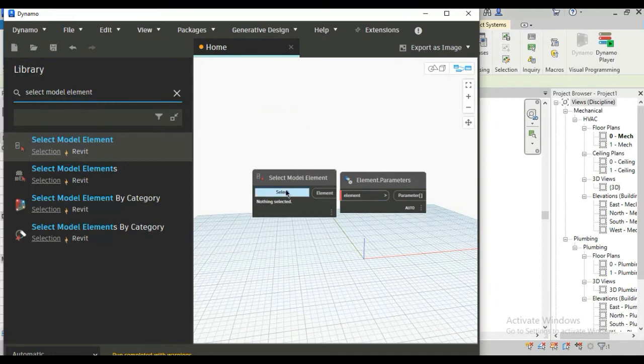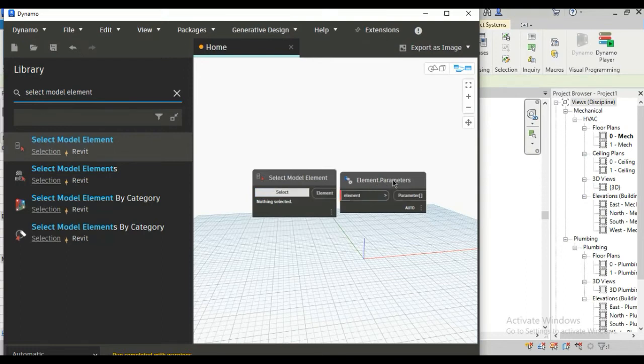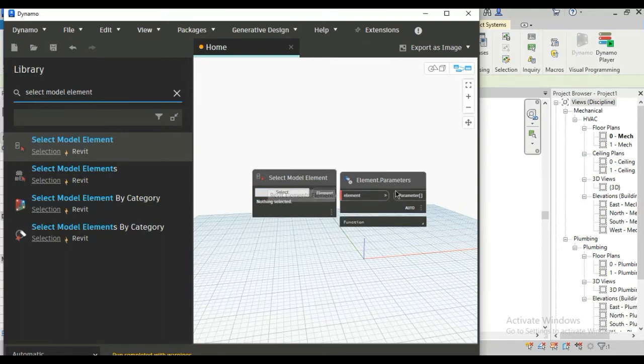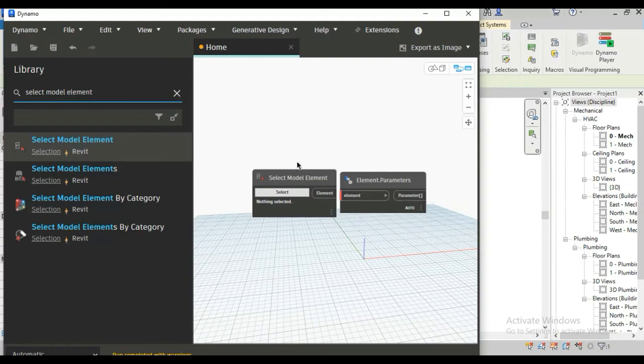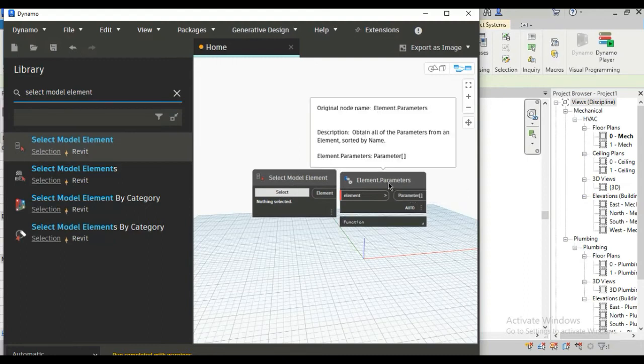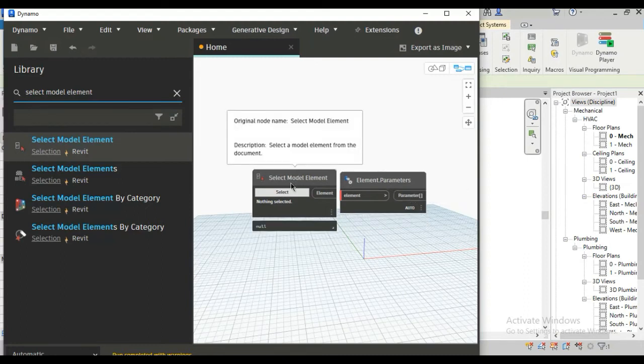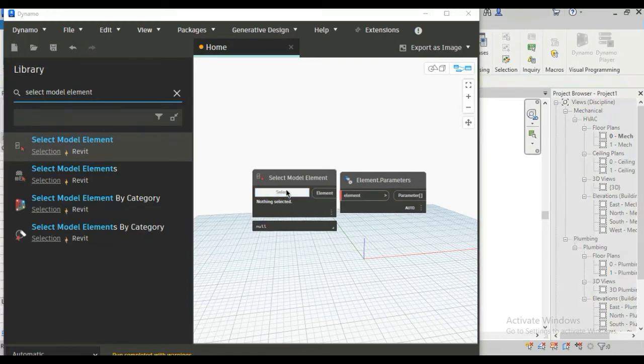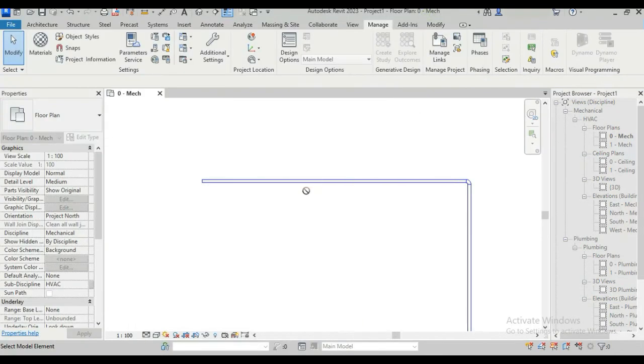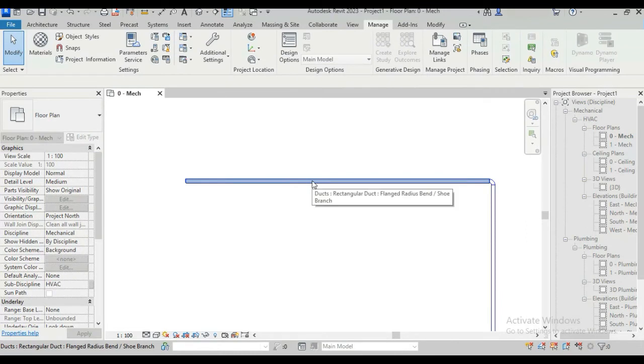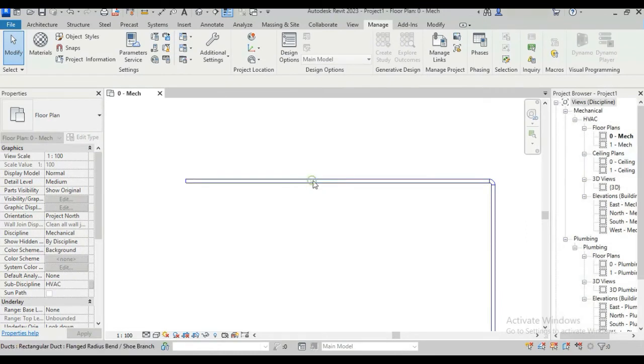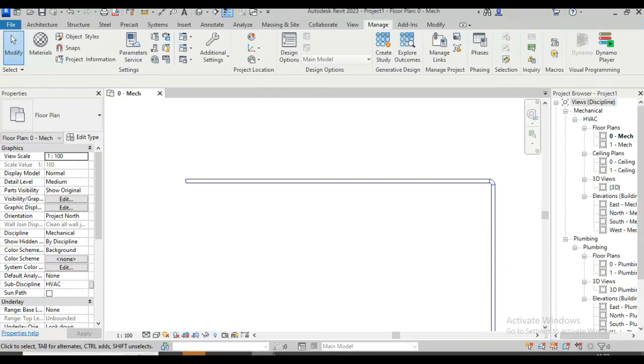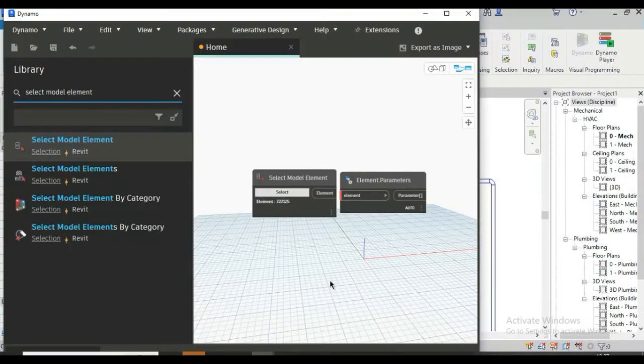Now in this node element selection is input and element is output and in this node element is input and parameter is output. So using first node we can select any element for dynamo, just simply click on select and go to Revit and click on this duct and go to the dynamo again.